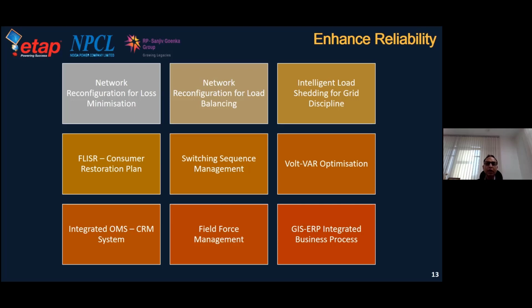The other features of DMS applications are network reconfiguration, through which we can do loss minimization on the one side, and also load balancing on the other side. Network reconfiguration for load balancing is a part of it, or it can be separately handled within the overall applications theme. Intelligent load shedding for grid discipline: for example, if frequency reduces below a threshold value, then we have the regulatory requirement to switch off the feeders. Similarly, another threshold point which can be set is the overloading condition. If, say, the power transformer overloading condition is set at 95%, then a few of the feeders are automatically shed by this application in case the overall load exceeds that particular threshold limit, here 95%. We have already talked about the FLISR switching sequence.